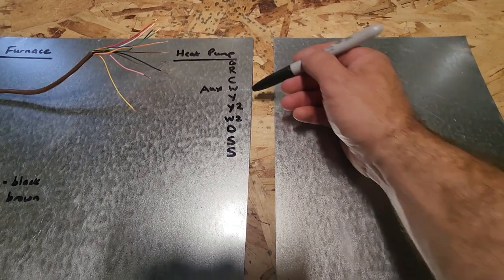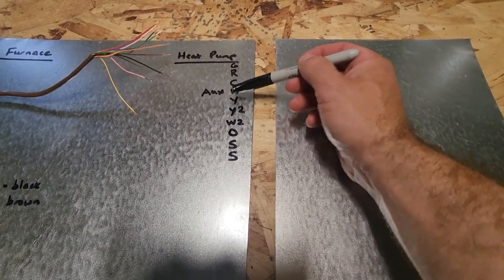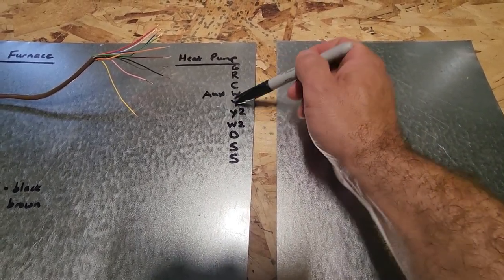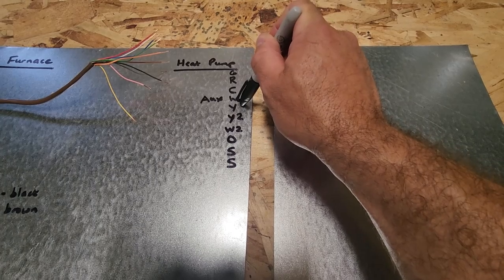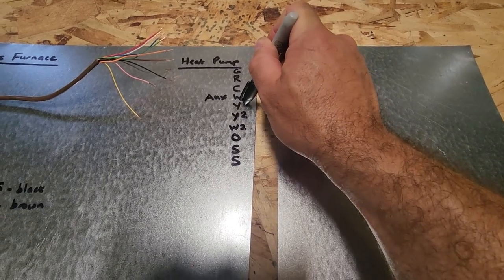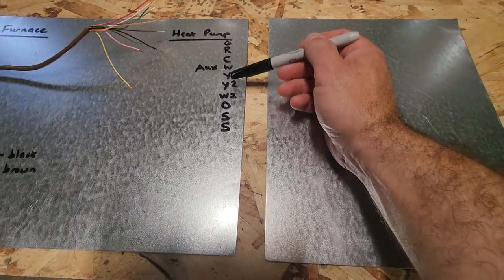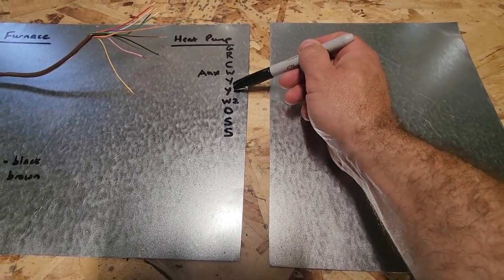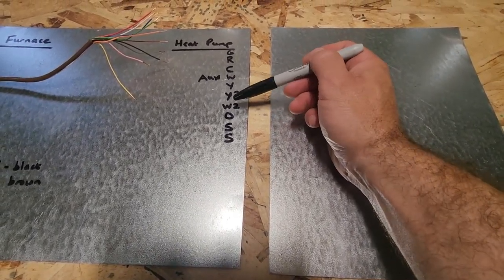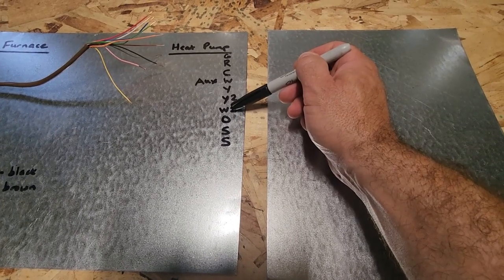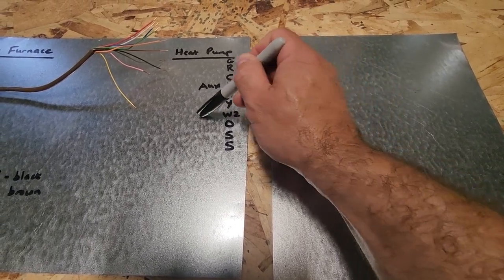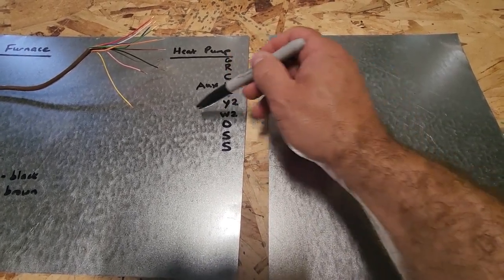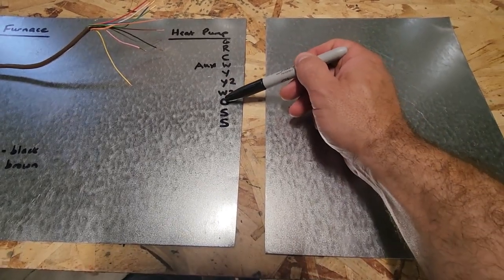Y in a heat pump is yellow still, but we call that first stage compressor because all that's doing is energizing your outdoor unit, okay? Just like in an air conditioner, but it also produces heat. Y2, second stage compressor, second stage condensing unit. W2, if you had 2 stages of strip heat and you wanted to stage them, that's what that would be for. Now O, that's different.